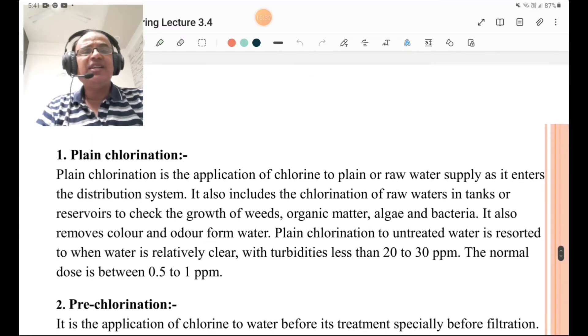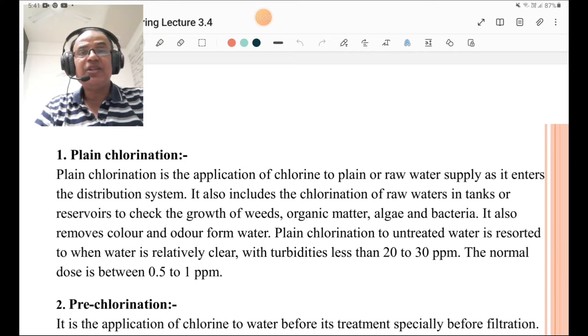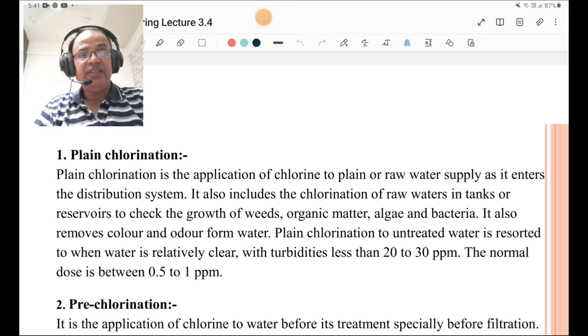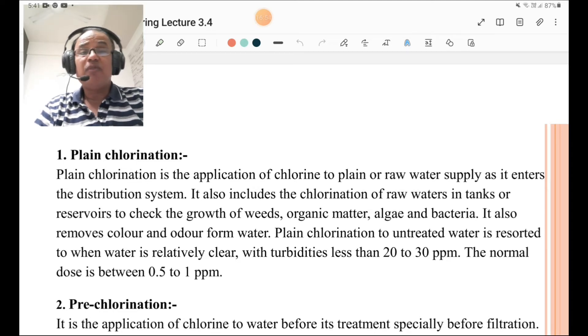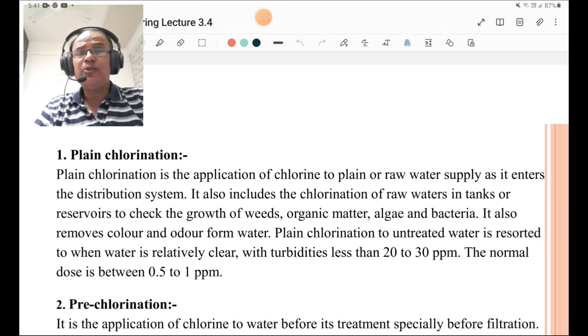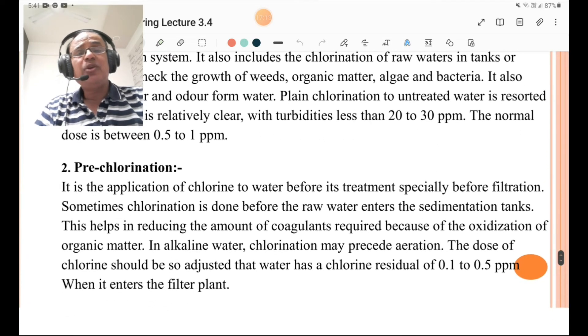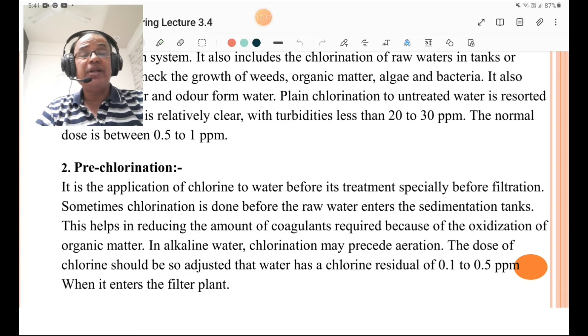Plain chlorination is the application of chlorine to plain or raw water supply as it enters the distribution system. It also includes chlorination of raw waters in a tank or reservoir to check the growth of weeds, organic matter, algae, and bacteria, and also removes color and odor from water. Plain chlorination of untreated water is resorted to when water is relatively clear with turbidity less than 20 to 30 ppm. The normal dose is between 0.5 to 1 ppm.